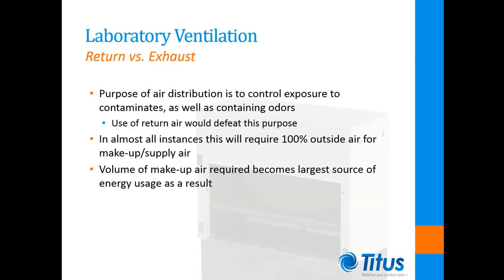I have been referring to the air being removed from the space as exhaust and not return, and this is for very good reason. As we have discussed, one of the purposes of air distribution is to control exposure to contaminants as well as containing odors. In both cases, return of this air to the air handler would defeat the purpose of having these control mechanisms in place. As a result, almost all lab spaces will require 100% outside air for the primary system.